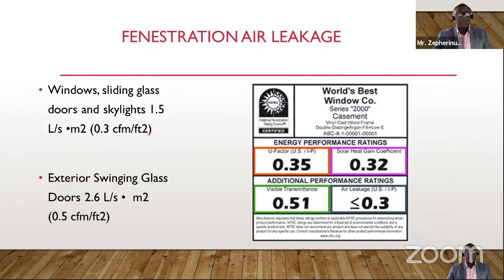The same thing for your exterior swinging glass doors. The requirement would be 2.6 liters per second per square meter. Now, the code uses the SI units as the preferred unit of measurement, and you will see in some cases the corresponding imperial units next to the requirements, as you can see here. Now, this is a typical label for fenestration, and this label is from the National Fenestration Rating Council in the US, where they would now give you the different parameters, whether it's the U factor, the solar heat gain coefficient, the visible transmittance, and the air leakage.